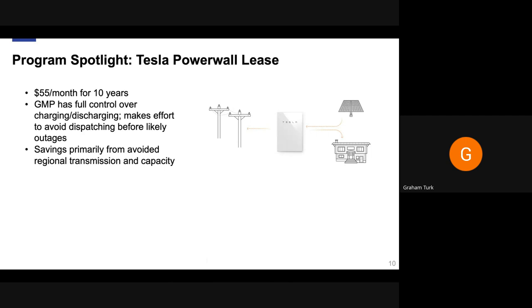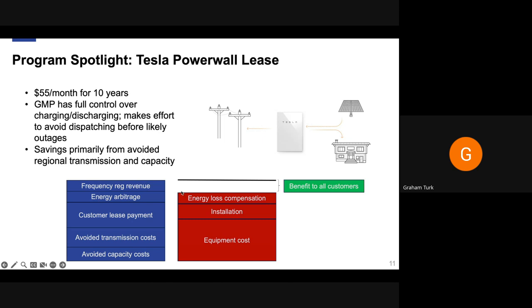Unlike some other programs, we weren't sending event notifications — these ran in the background. We made all our best efforts not to dispatch whenever there was increased likelihood of an outage, which is a huge point of tension for batteries used for backup, especially in California where PSPS wildfire safety shutoffs sometimes coincide with periods you need to draw on the battery. The value from this program came from dispatching against peaks. We projected 10 years of avoided capacity and transmission costs. Customers paid a lease — a discounted version of what they'd have paid buying the battery outright from Tesla.